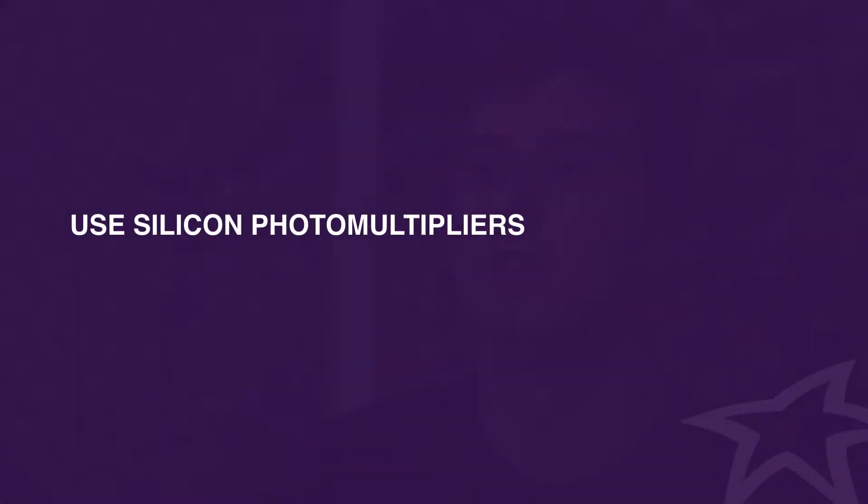Hi, my name is Peter Kazikoff. I'm an electrical engineer at Starfish Medical. I've been working here since I graduated in 2015, on everything from very small medical devices to large carts, from ultrasound to fluorescent assays and everything in between. Many assays require detecting very small amounts of light — on the order of a few hundred or thousand photons per second. Previously, this required large benchtop instrumentation using vacuum tubes. With a recent technology called a silicon photomultiplier, we can now shrink what was only possible on the benchtop down to a very small, low-power, low-cost medical device. We did this for a client — taking a large fluorescent assay that required big benchtop equipment and shrinking it to a form factor of only five milliliters.